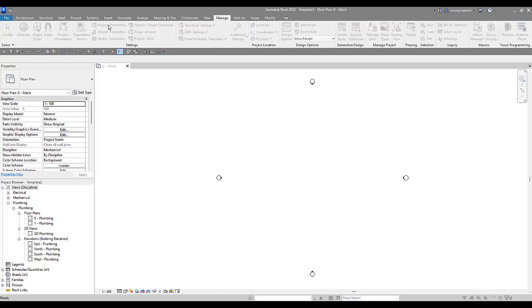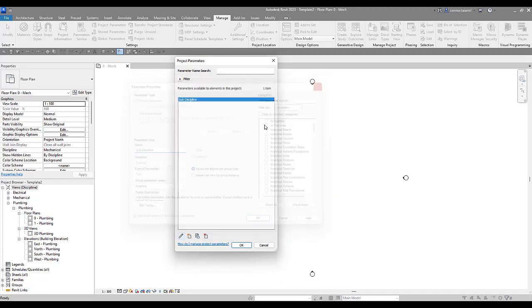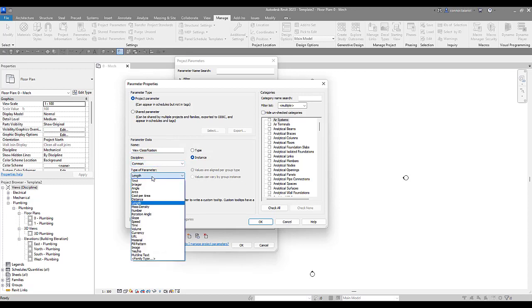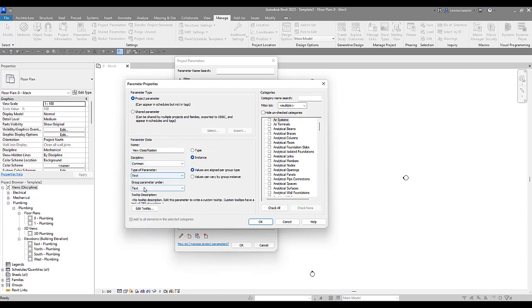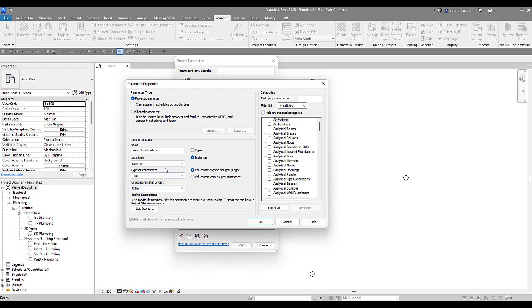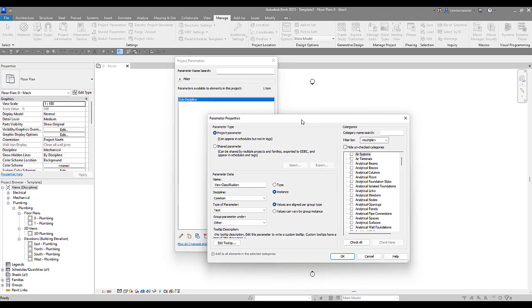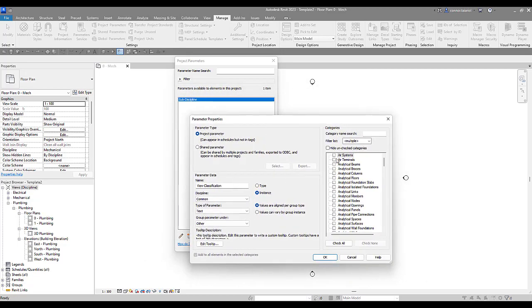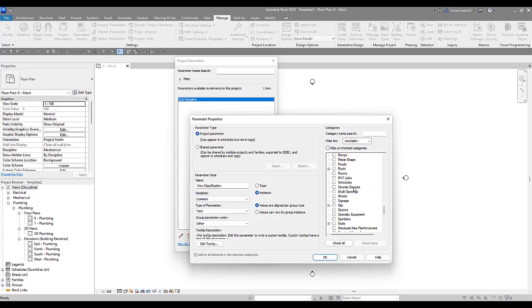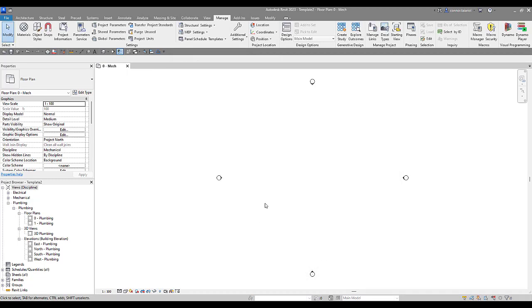We're going to come up here, we're going to add a project parameter and they've got one in here called Subdiscipline. We're going to create another one. We're going to come down here to the little star, go new. We're going to create another one called View Classification. Type of parameter is going to be text. We're going to group it under Other. Project parameters allow us to create parameters and assign them to different categories. On that right hand side here, we're going to assign this to views. We want to be able to access this within our views. When we create a new view, we want to give it a new view classification. So scroll down, select on Views and then press OK.